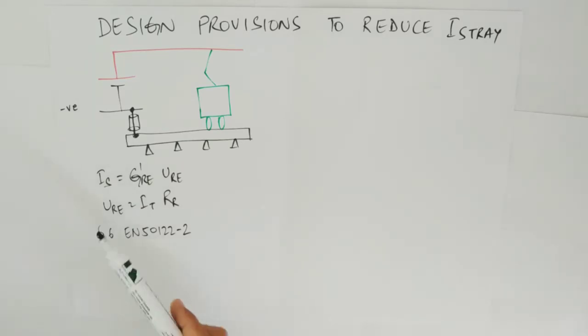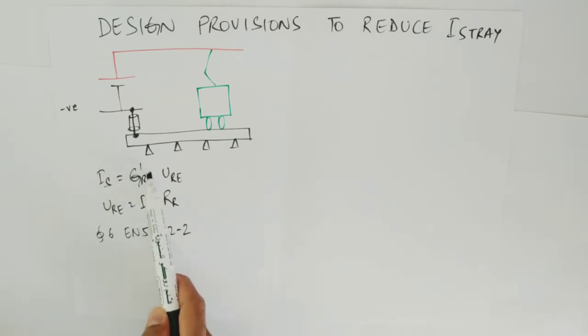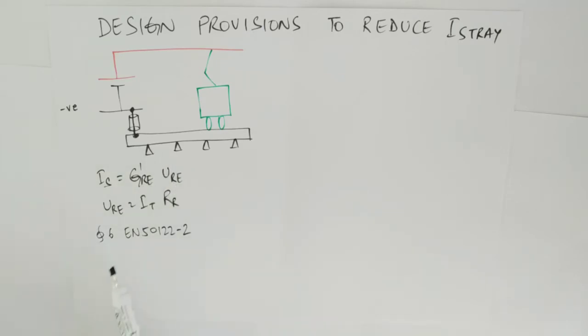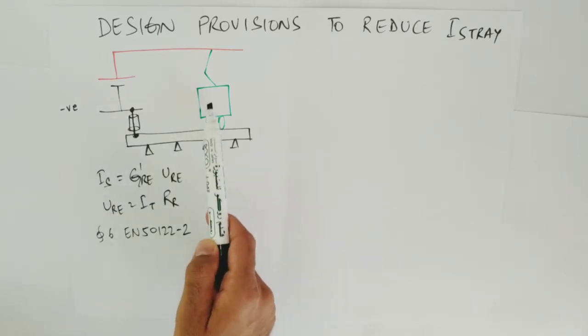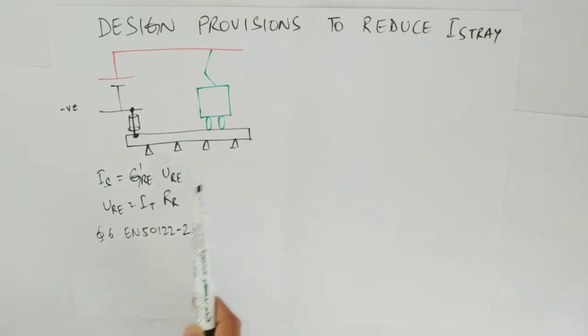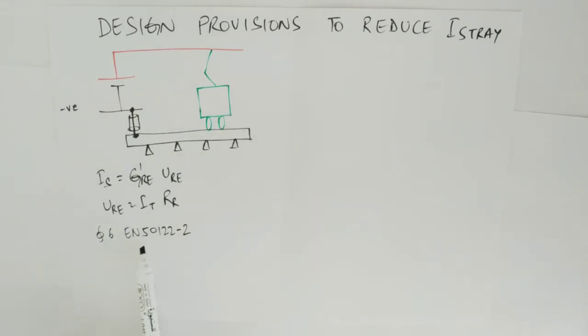In the previous lectures we have seen these two formulas: the stray current is equal to the product of the track-to-earth conductance times the running rail potential, and the running rail potential is the product of the traction current times the running rail resistance — that is the longitudinal resistance of the running rails. The design provisions we are going to discuss are mentioned in clause 6 of EN 50122-2.